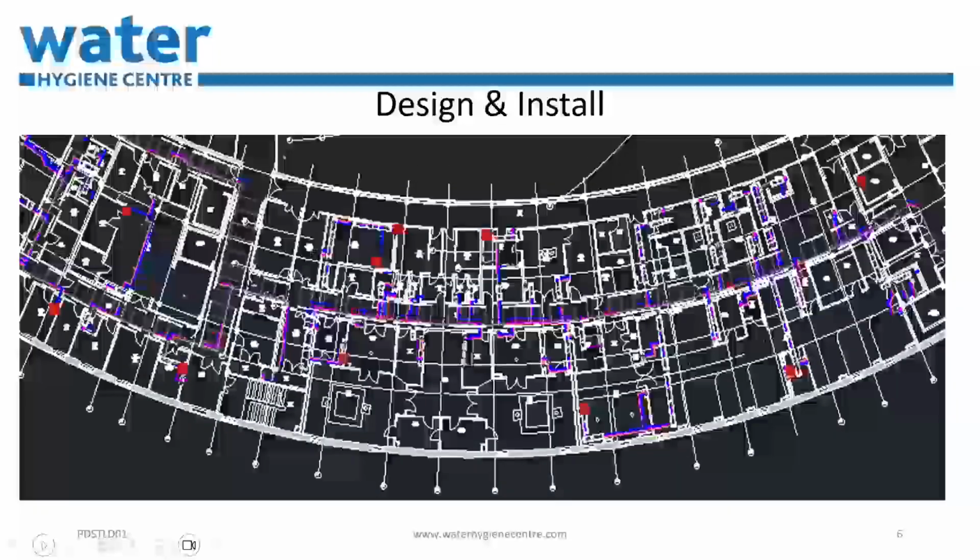And HSG 274 Part 2, paragraph 2.4 details stagnation of the water system during construction as being a potential issue for biofilm formation, and as such, twice weekly flushing alone will not suffice. Contractors do not appreciate that water sat around only being flushed twice a week presents a risk, especially when they've left site. So the key there is how is the actual process designed?